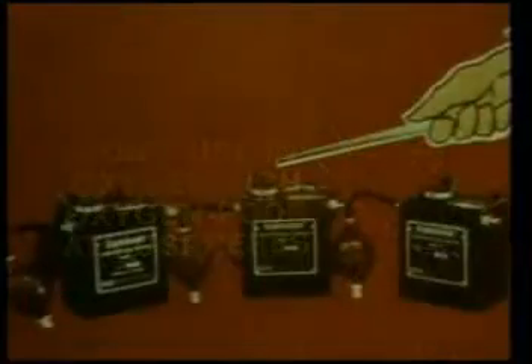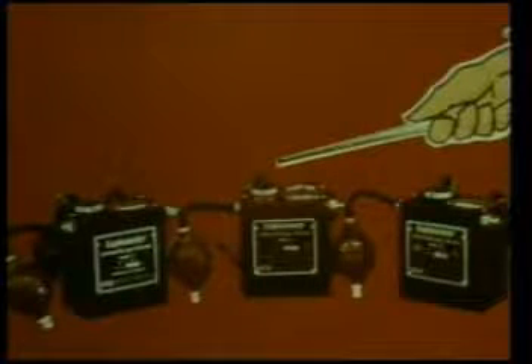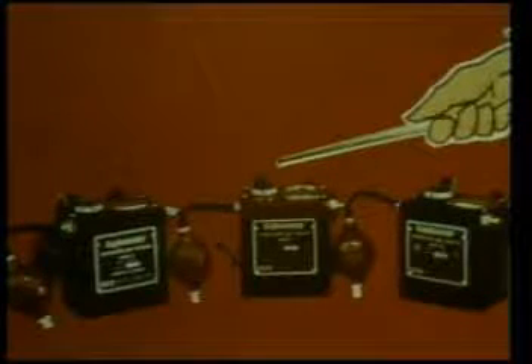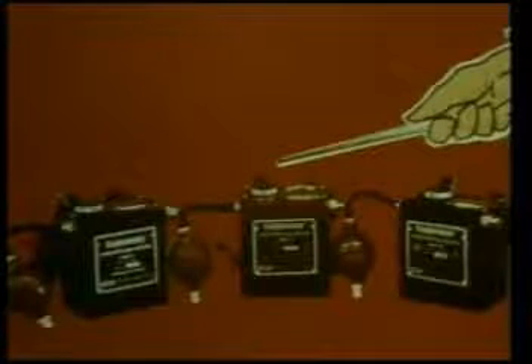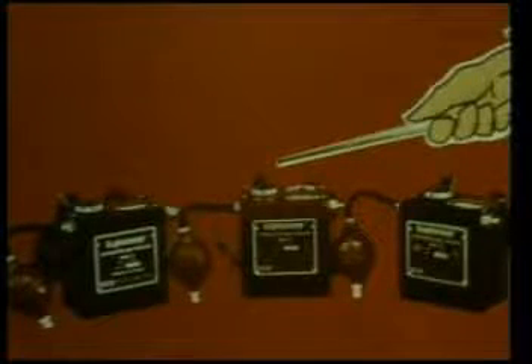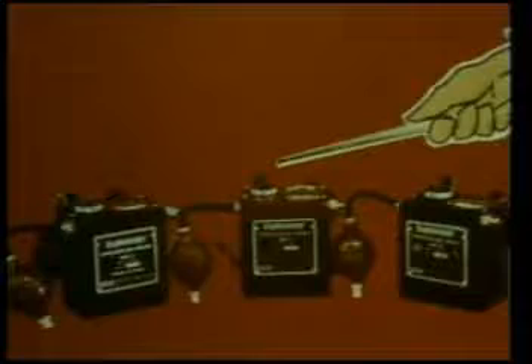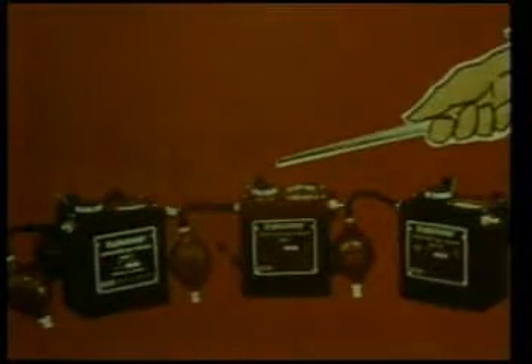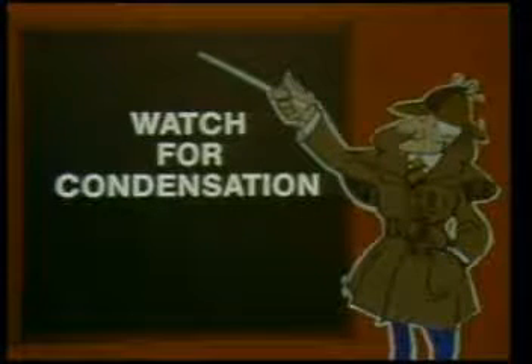Also, there are special models of the explosimeter indicator with heavy-duty flashback arresters to keep explosions of mixtures of oxygen and hydrogen, or oxygen and acetylene, within the combustion chamber. Further, if you try to test solvents with a high flash point and the temperature of the test area is higher than the temperature of the instrument, there may be some condensation of combustible vapors in the sampling line and flow system. As a result, the instrument may not show the true concentration.